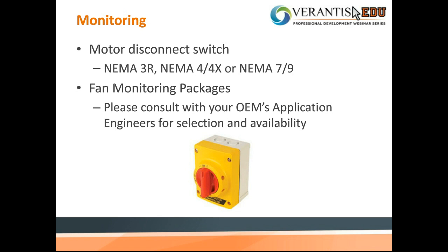With monitoring, we've also included motor disconnect switches. If a motor disconnect switch is required, make sure the NEMA rating fits your environment. If a NEMA 4 is required, or a 4X, or a 7, or a 9, the OEMs typically can supply these, but we just have to make sure it's the right rating for your environment. We don't want to have a hazard started by the motor disconnect switch. As for fan monitoring packages, please consult with your OEM's application engineers for selection and availability. They will be more than willing to help you out or provide something in this direction.